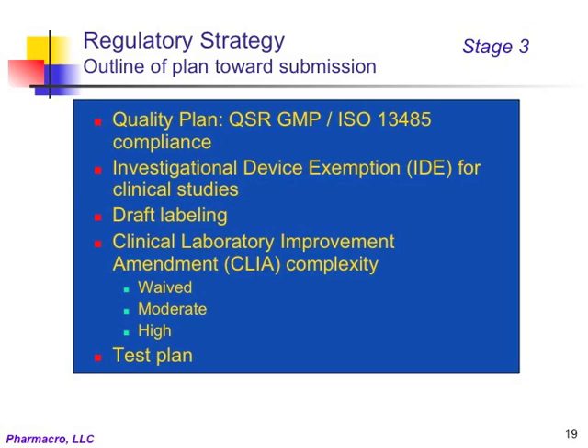If a clinical study is required to get approval of the product, then an investigational device exemption or IDE is needed for conducting clinical trials with an unapproved device. Also needed is a draft labeling that includes all printed matter that will accompany the device when it is sold commercially. The CLIA complexity category will define the test plan that will need to be executed.